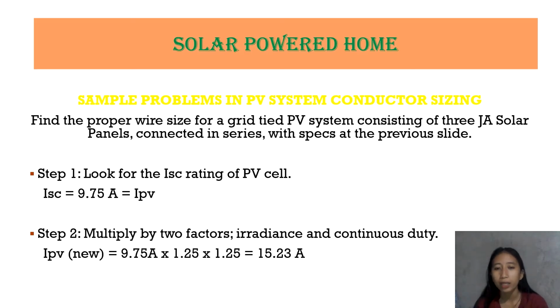So, step 1, ang sabi kanina is look for the ISC rating of PV cell. So, sinabi kanina na ang ISC rating daw is 9.75 ampere, which is equal to IPV. Okay, so step 2, multiply by 2 factors, irradiance and continuous duty. So, yung IPV natin is equal to 9.75 ampere times 1.25 times 1.25.25. Okay, so that is equal to 15.23 ampere.